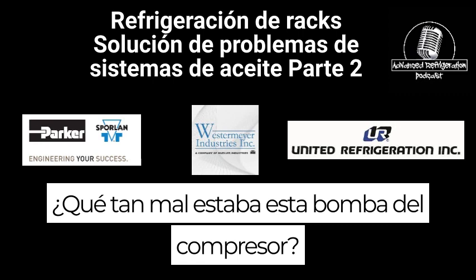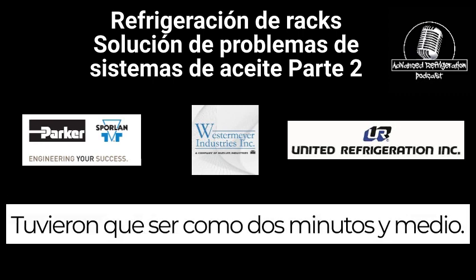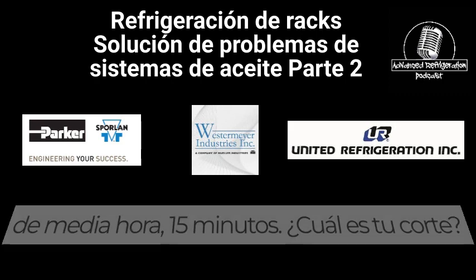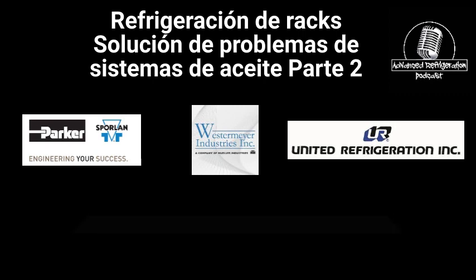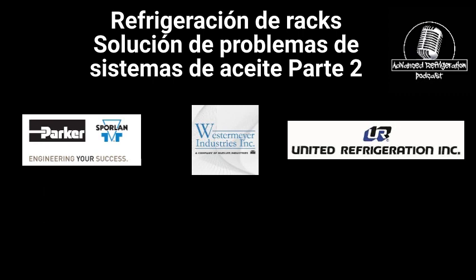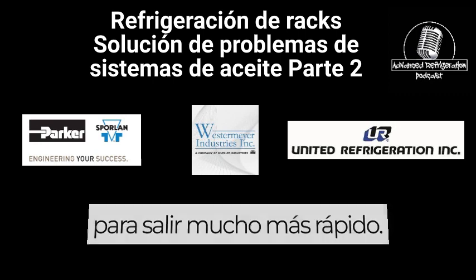So that compressor pumped out in less than 5 minutes. It had to be like 2.5 minutes. But if you have a compressor pumping out faster than half an hour, 15 minutes, what's your cutoff before you're going to start really investigating tearing that compressor cover off? Probably half an hour. Scrolls seem to pump out a lot faster.